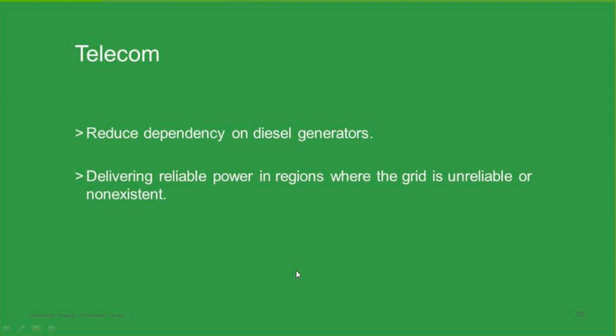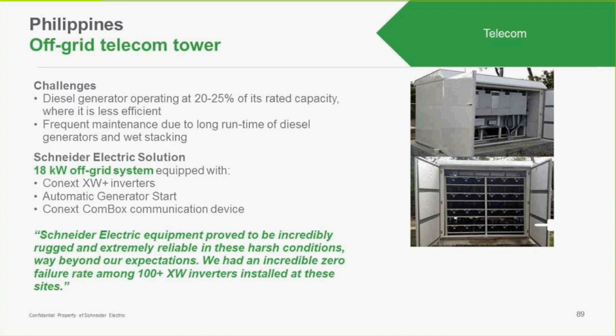And of course, telecom, where a lot of telecom towers run on diesel generators consuming about 2,500 watts of power, and getting a PV system connected to them saves on diesel fuel and makes the whole system more reliable. And as you can see, these are packaged in an outdoor enclosure, and when they get packaged in an outdoor enclosure, you have to take care to ensure there's enough ventilation, especially for the batteries. The inverters will handle anywhere from minus 20, 25 degrees up to plus 60 degrees, but they do derate with temperature.